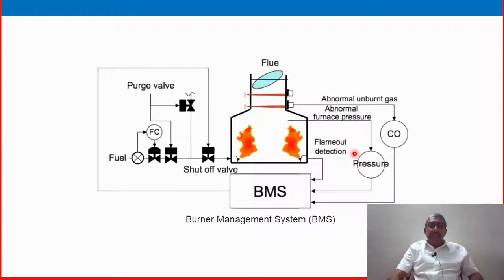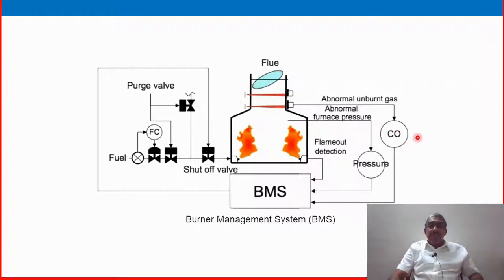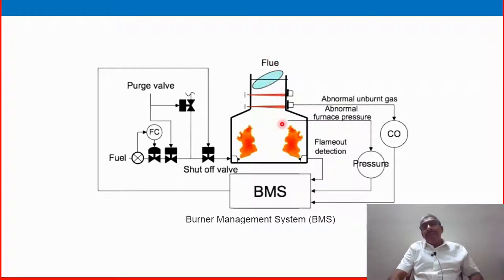In a proper combustion reaction, hydrocarbon — for example CH4 — burns with air: oxygen reacts and the resulting products are CO2 plus H2O. However, if combustion is incomplete, carbon cannot convert 100% to CO2, so unburned CO is produced and escapes to the atmosphere through the flue or stack. CO is highly toxic, so a CO sensor is used. If the CO level rises above normal, it triggers an alarm or trip logic to the boiler or burner management system.